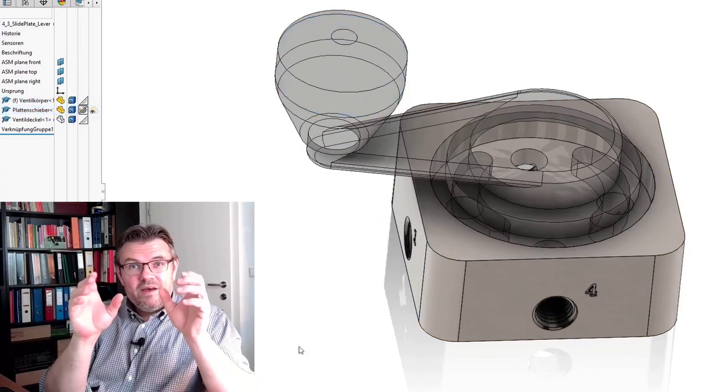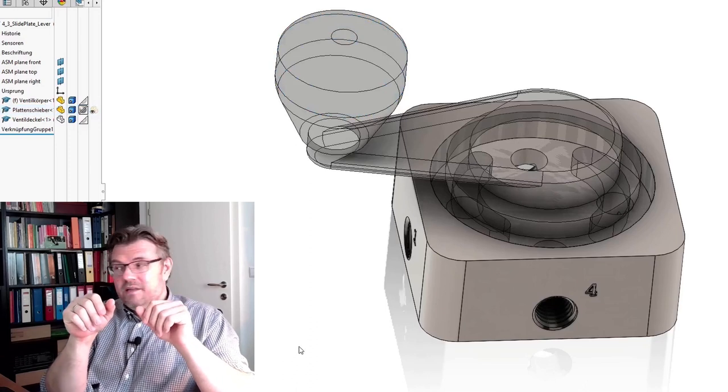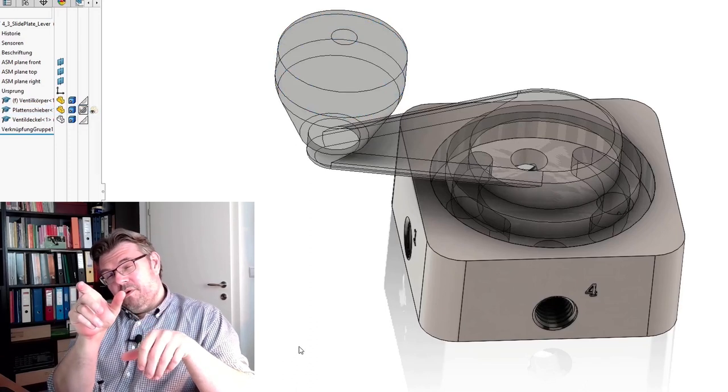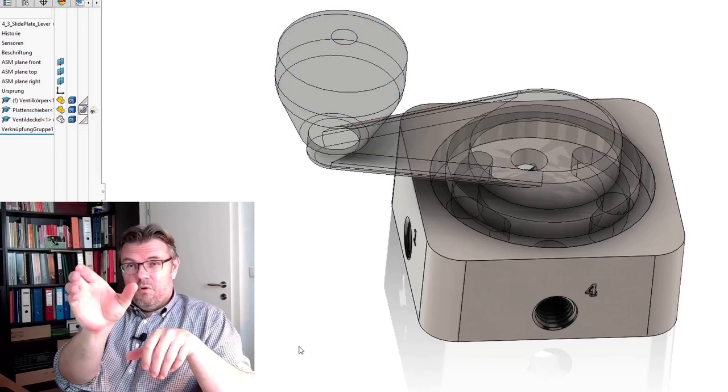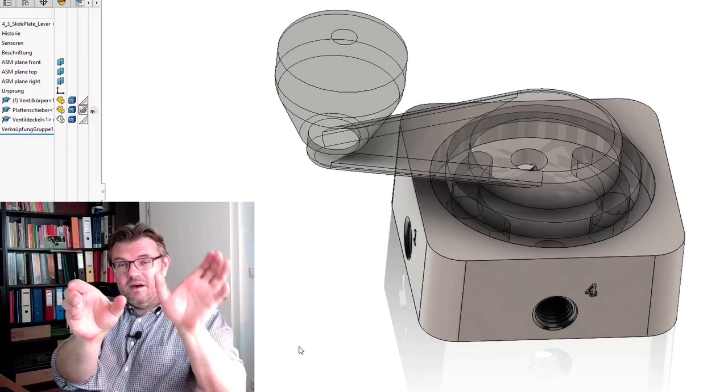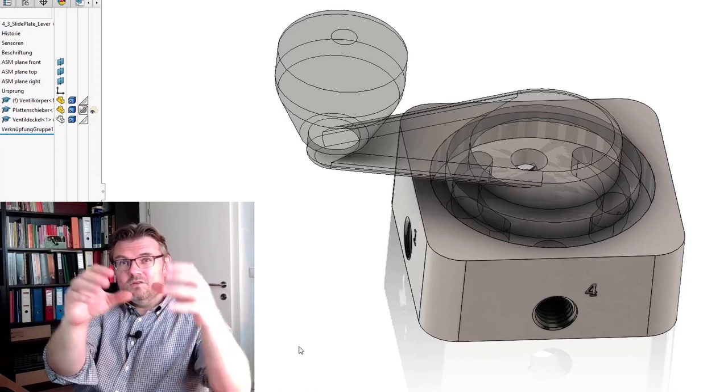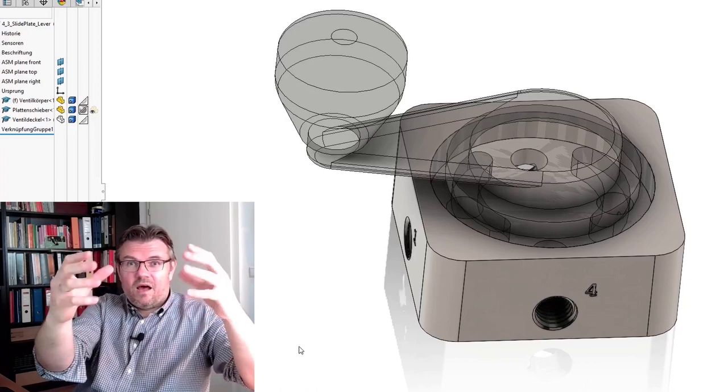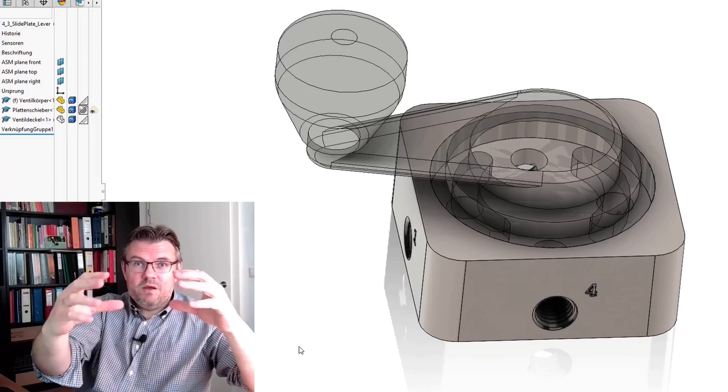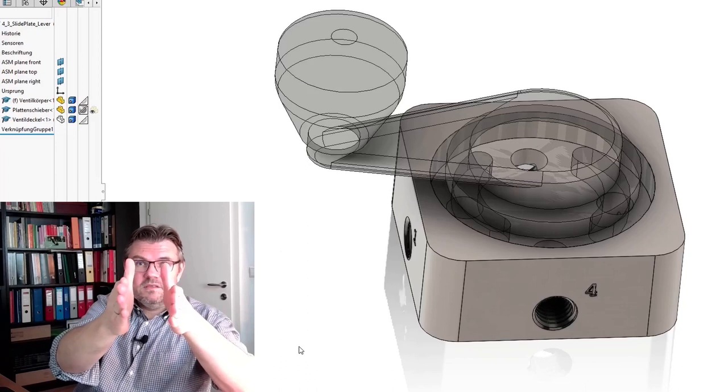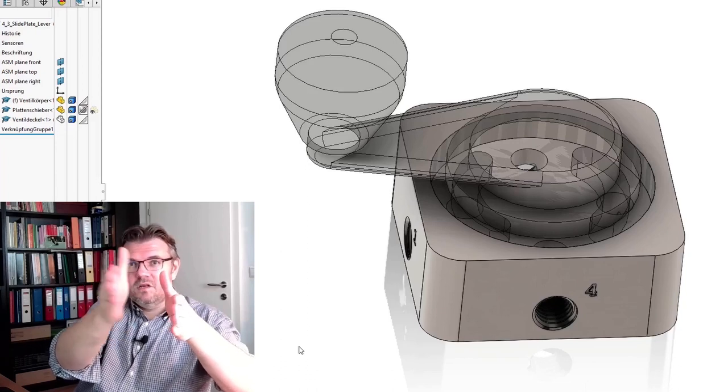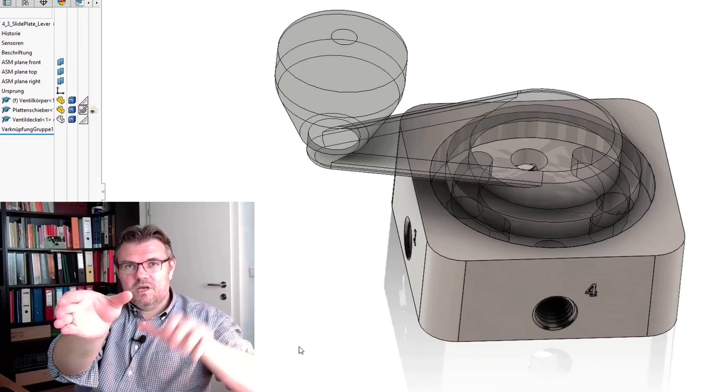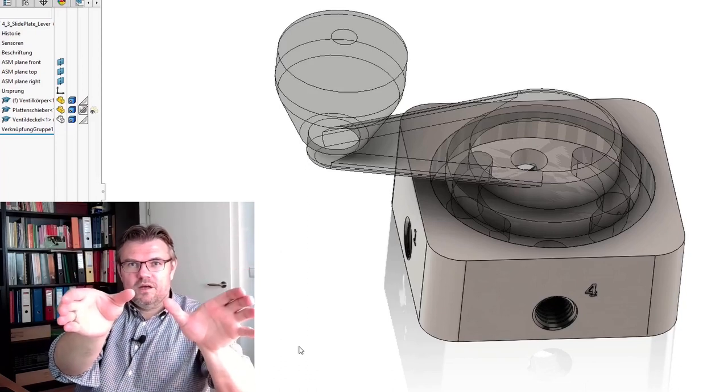Since if you have a double-acting cylinder and you are blocking one side air and the other side air, so the air cannot get out of any chamber, it will simply stay where it is. Because there is a pressure cushion on one side, pressure cushion on the other side, so it will not move.